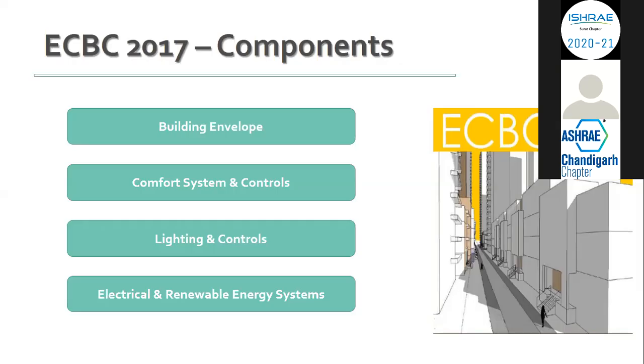Second, you must meet the basic requirements. If you have a split or window air conditioner, it must be a 3-star rated split or window air conditioner. If you are using a VRF system or centralized air conditioning, ECBC requires your VRF system to have a COP value of at least 3.6, and centralized air conditioners like screw chillers or centrifugal chillers must have a COP value of 5.6.